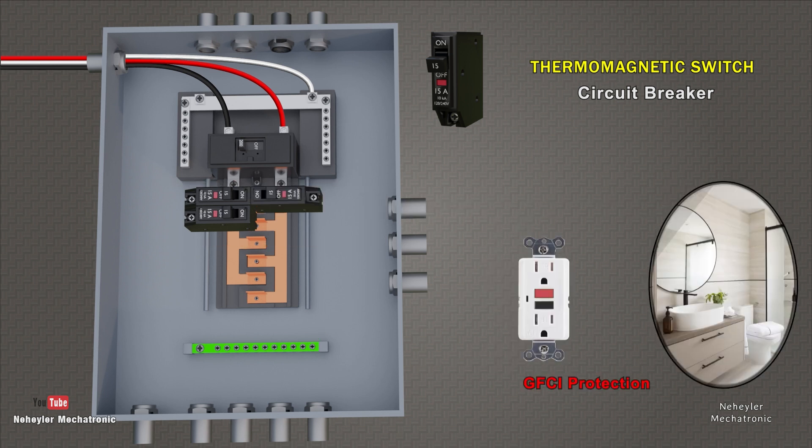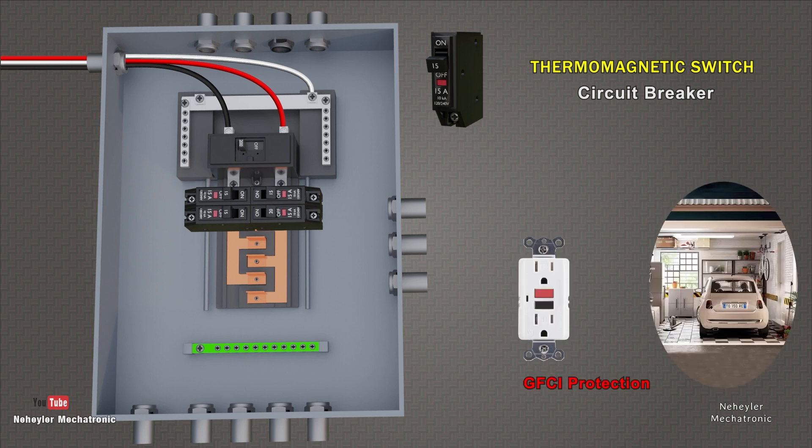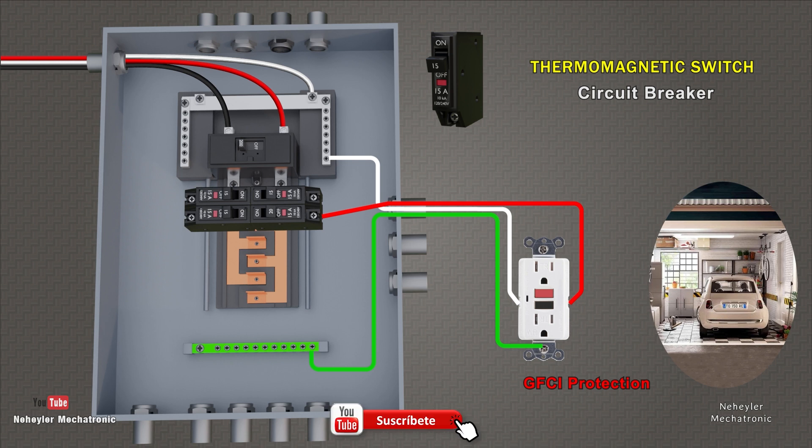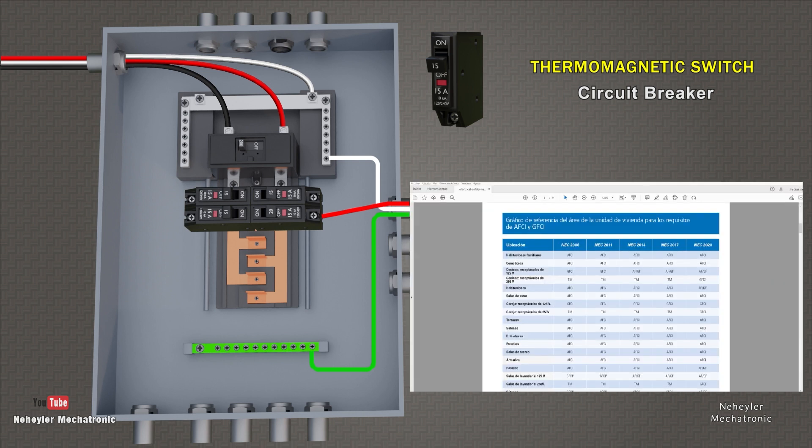Also, a circuit for bathroom contacts or outlets will be considered. We must take into account that these elements have GFCI protection, that is, against current leakage to ground. The breaker could also have this protection. Another breaker would also be used for the garage part, which should consider a GFCI protected outlet. Previously this was not considered, but according to the current code 2020 it is considered. In the video description, I am going to leave you the reference table with the protection requirements for each part of the home.